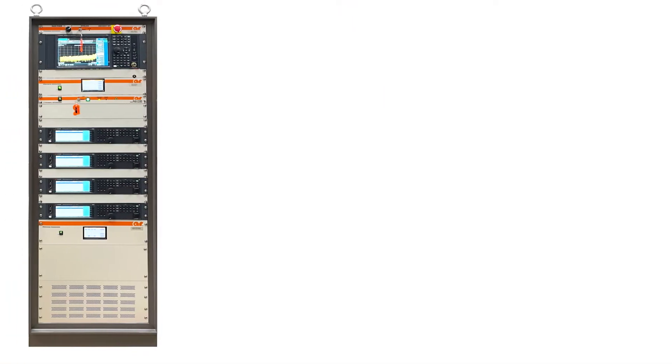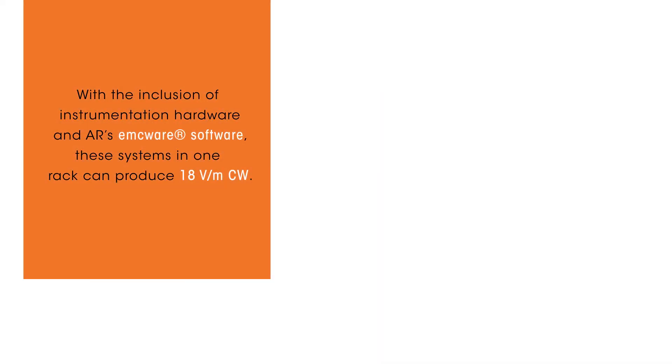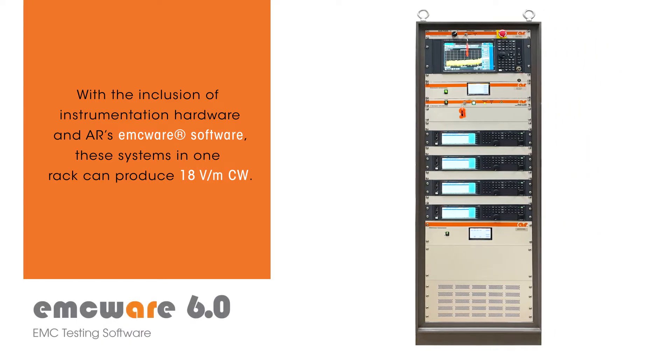AR's multi-tone test systems are state-of-the-art systems designed to test RF radiated and conducted immunity faster than ever, allowing the ability to test up to four tones at one time. With the inclusion of instrumentation hardware and AR's emcware software, these full turnkey systems in one rack can produce 18 volts per meter CW.